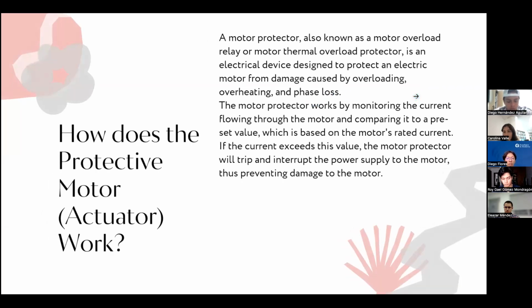And how does the motor protector work? A motor protector, also known as a motor overload relay or motor thermal overload protector, is an electrical device designed to protect an electric motor from damage caused by overloading, overheating, and phase loss. The motor protector works by monitoring the current flowing through the motor and comparing it to a preset value, which is based on the motor's rated current. If the current exceeds this value, the motor protector will trip and interrupt the power supply to the motor, thus preventing damage to the motor.